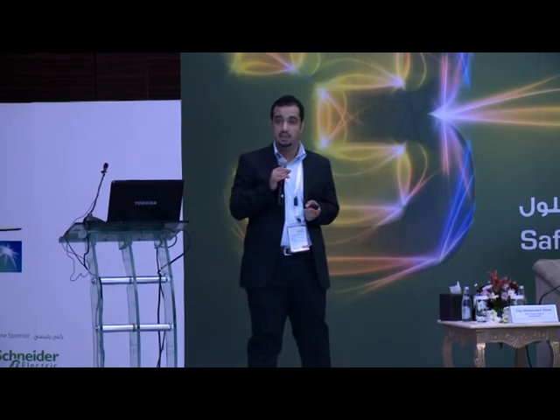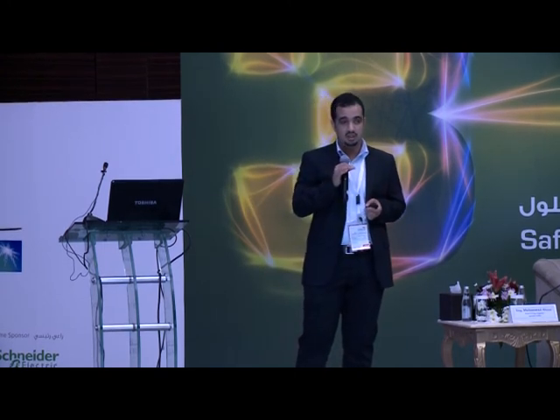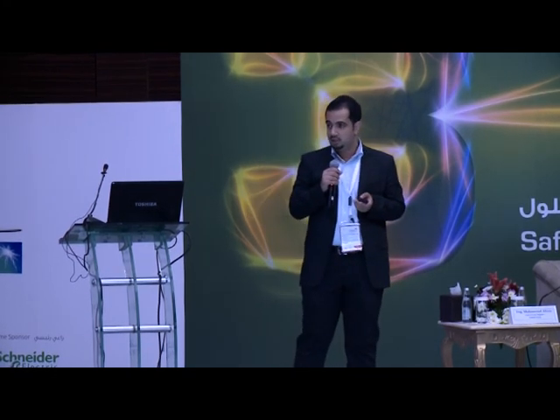As many of you know, arc flash energy is quantified in calories per centimeter squared, where 1.2 calories per centimeter squared could cause a second-degree burn if it is directed to the skin for 1 second. Actually, the purpose of this presentation is not to talk about arc flash history. Nonetheless, I will remind you of some facts and fictions when it comes to arc flash safety.